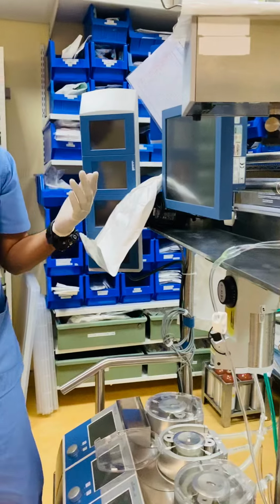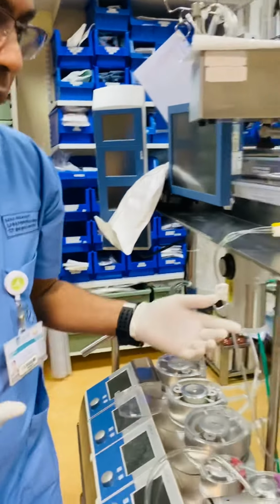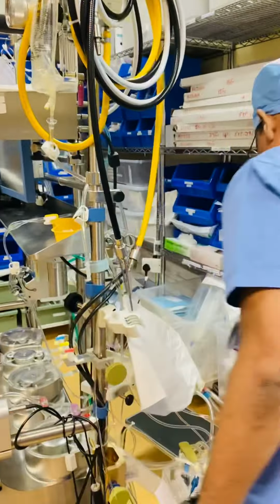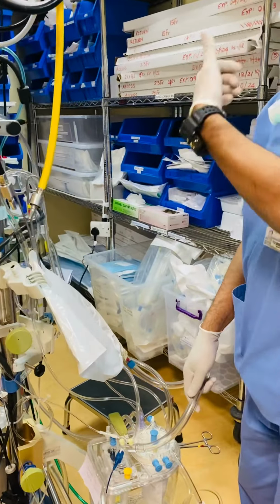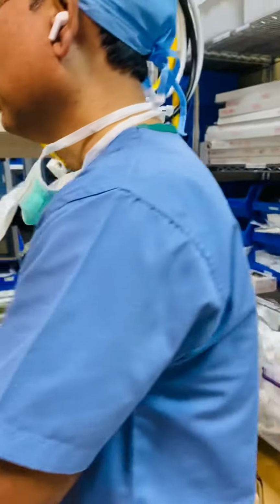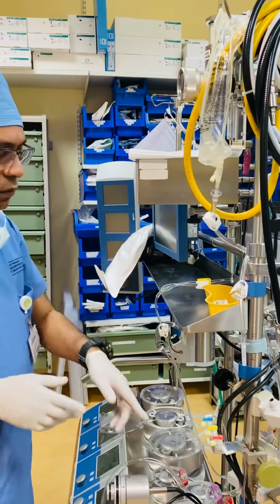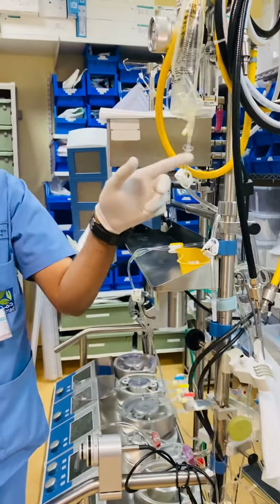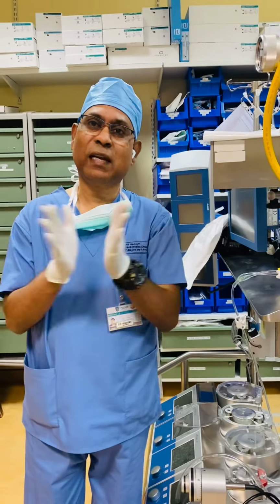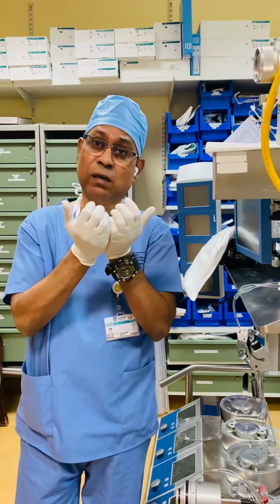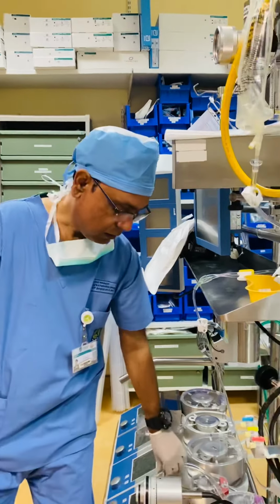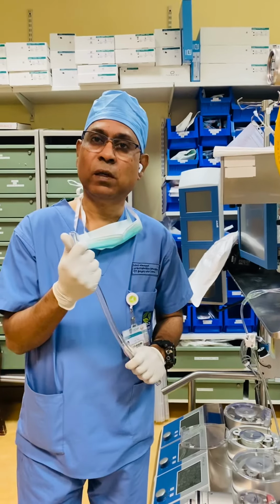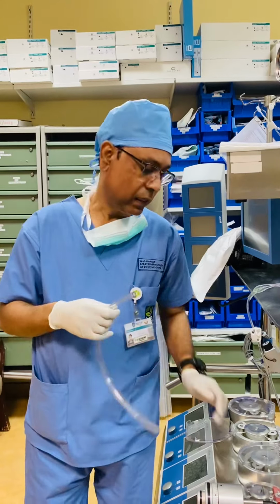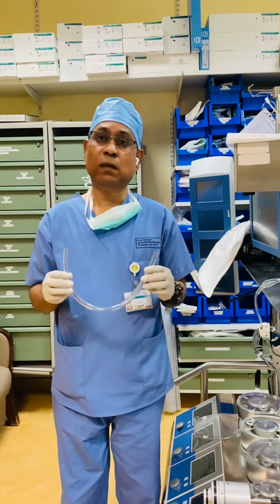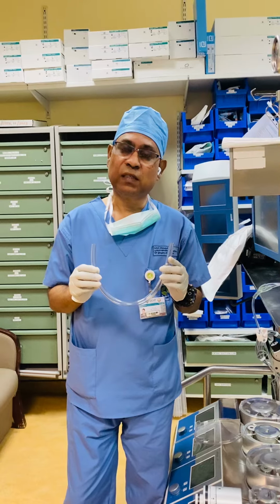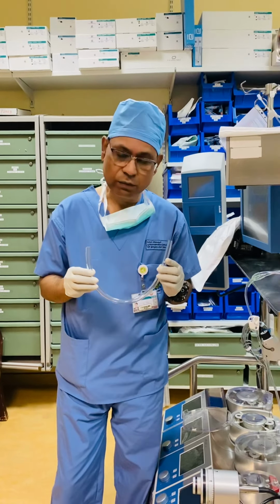Now one more example. If you use the silicone tube here to suck blood from the body, what will happen? If the silicone tube is connected as a venous line and connected to the venous cannula, it will collapse and you will not be able to suck blood from the body. This is the reason we need a rigid tube for sucking and carrying. But inside the roller pump, we require the flexible tubes, which cause less destruction of the cells.